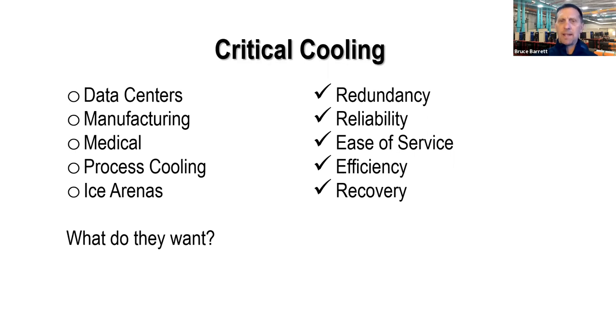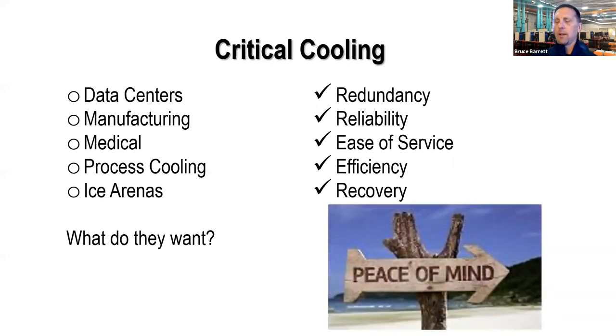A modular chiller may not be a fit for every job. If they want the lowest cost, chilled water, comfort cooling, probably not a good fit. But if there's some need for redundancy, reliability, service, backup, free cooling, and that recovery time, does that customer want a certain peace of mind on this project? Modular might be the way to do it.